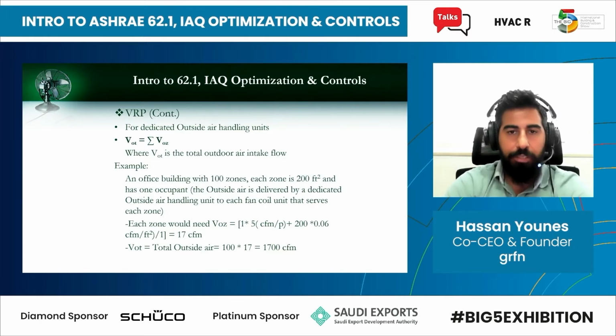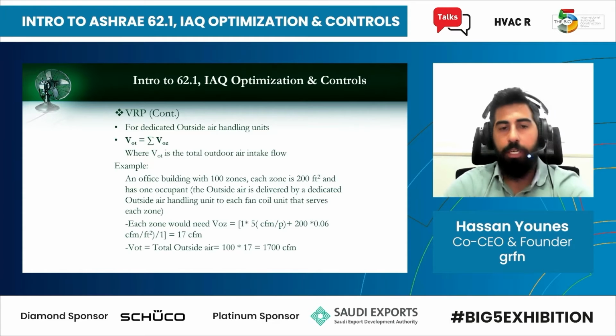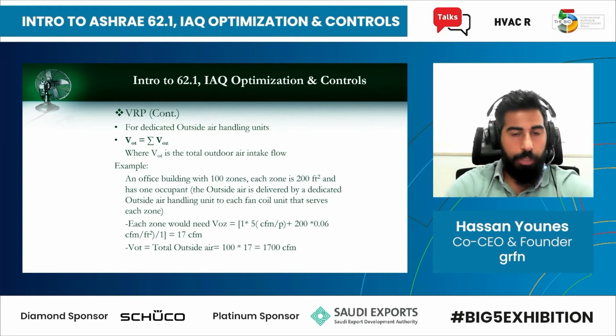Now, if you have a dedicated outdoor air system and you are supplying through what we sometimes call fresh air handling units to individual zones, then just adding all those zone flows will give you the required outside air intake on that fresh air handling unit or outside air handling unit. As an example, if you have an office building with 100 zones, each zone is 200 square feet or 20 square meters, and each zone has 1 occupant, then each zone would require 17 CFM, or around 8.5 liters per second. With 100 zones, you multiply that by 100, and we end up with 1,700 CFM for the whole outdoor air handling unit, which is almost 850 liters per second. So this is how we calculate how much outside air is required for that particular outside air handling unit.